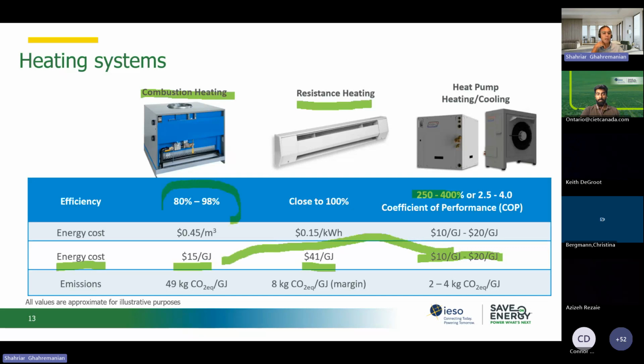One of the reasons is that natural gas burning systems are not that efficient. If they are brand new systems, their efficiency is between 80 and 92 to 93%. If they are condensing units, for sure they are going to be above 90%. If they are non-condensing, which I don't think anybody buys, but they are still available and cheaper, their efficiency goes down to the 80% range. So if we include that efficiency, then the cost of energy or utility for us becomes comparable. That's a good sign for using heat pumps.